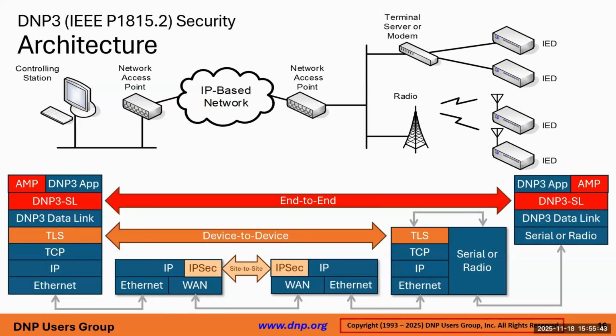And as you can see from the diagram, if you're dealing with IPsec, secure IP, that gives you security from network access point to network access point — that's the yellowish arrow at the bottom there, site-to-site security. And then above that, you may be using TLS, which is device-to-device security, but only from device to device, as long as you have an IP network underneath you — that's the more orangish arrow. So DNP3 security operates just below the application layer, at the session layer, and works end-to-end regardless of whether it's being carried over an IP-based network, a serial network, or a radio network, making sure that security is applied in all of those cases.